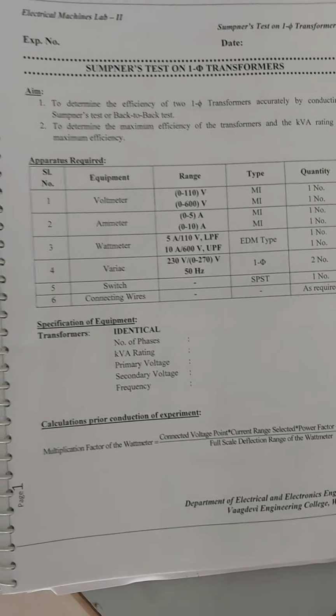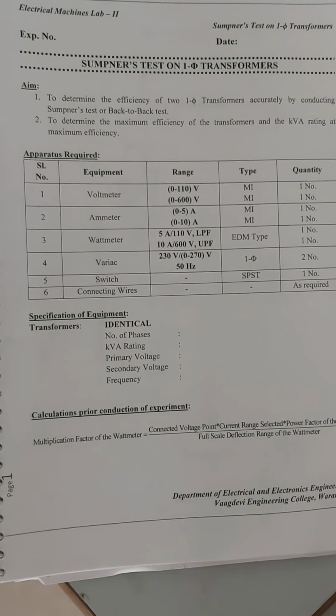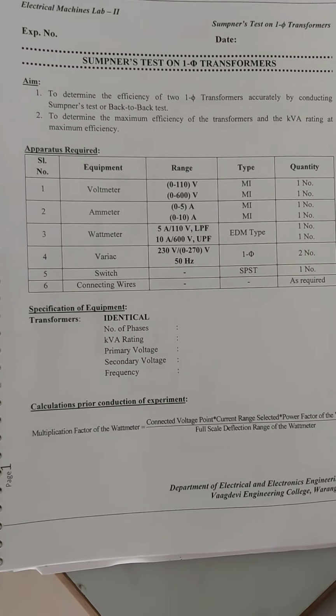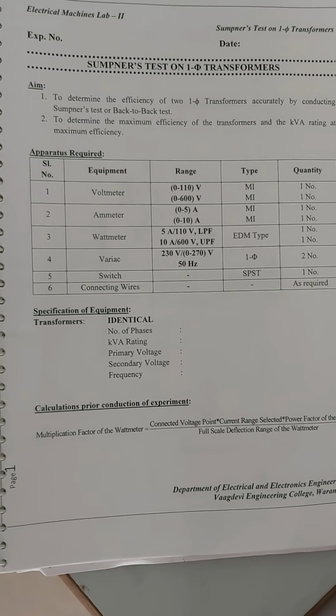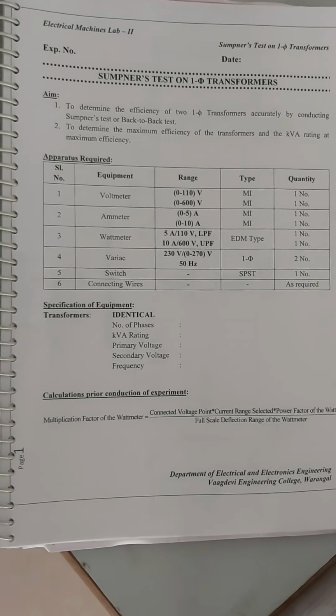This test is also known as the back to back test, and by conducting this test we can also determine the maximum efficiency of the two single phase transformers and the kVA rating at maximum efficiency.